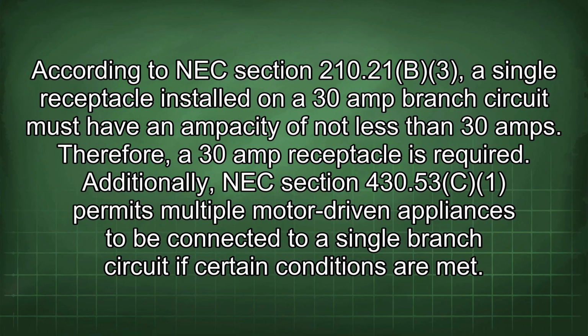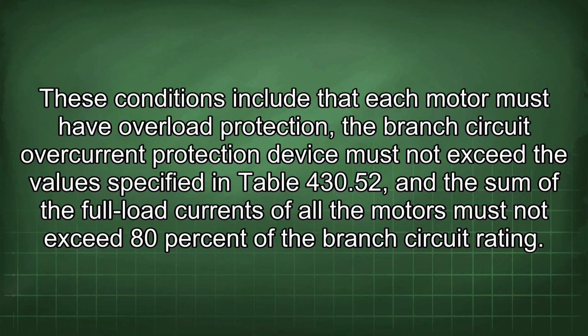Additionally, NEC Section 430.53 permits multiple motor-driven appliances to be connected to a single branch circuit if certain conditions are met. These conditions include that each motor must have overload protection, the branch circuit overcurrent protection device must not exceed the value specified in Table 430.52, and the sum of the full load currents of all the motors must not exceed 80% of the branch circuit rating.